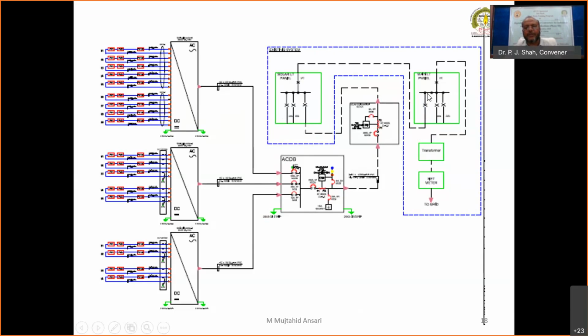From this generation meter, it is connected to the main distribution panel. While connecting to the main distribution panel, it should be ensured that the DG set power is not connected to the PV modules. In Maharashtra, we can only connect the PV modules with the grid, say the MSEDCL grid. It is not allowed to connect your PV solar plant with your generator systems. So whatever the changeover switch is, it should be ensured that during DG set operation, our PV modules are disconnected.